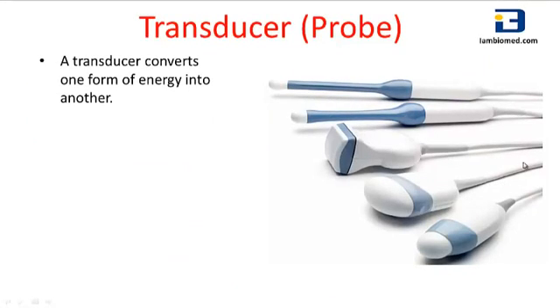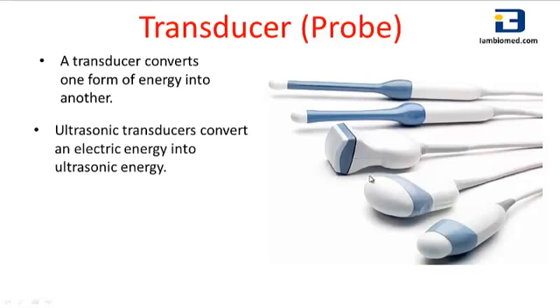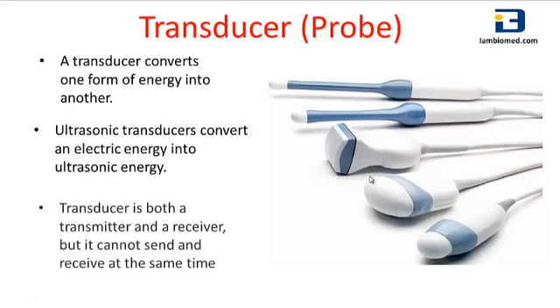The transducer converts one form of energy into another. Ultrasonic transducers convert electric energy into ultrasonic energy. The transducer is both a transmitter and a receiver, but it cannot send and receive at the same time.